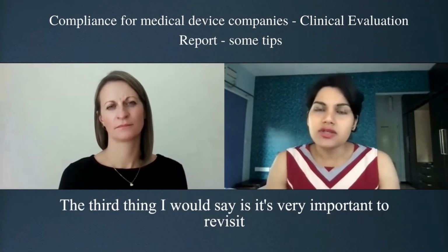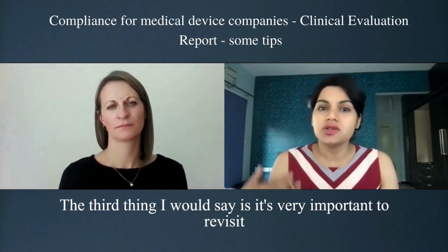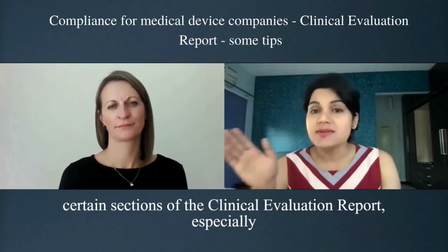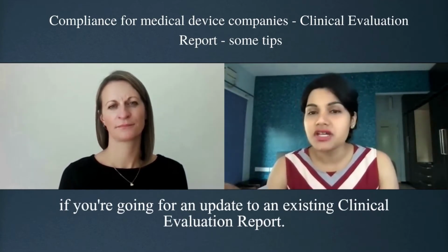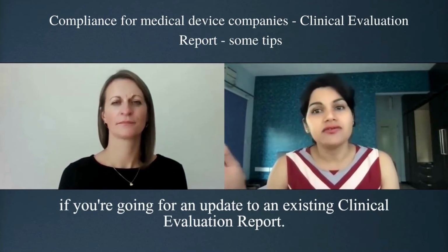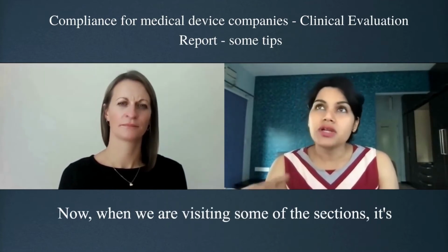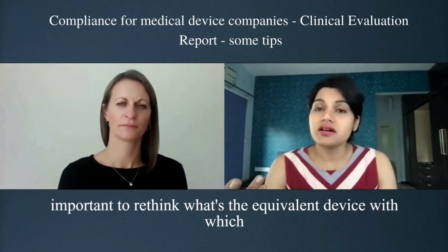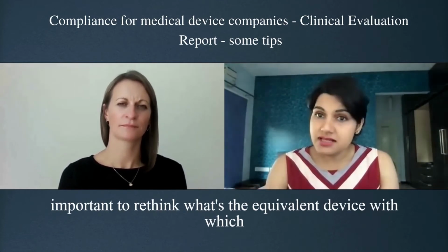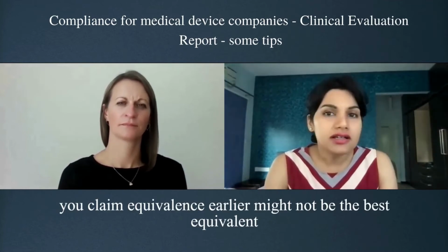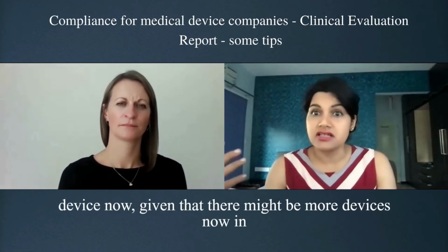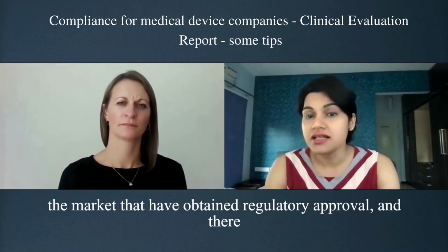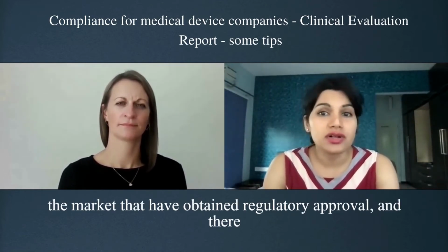That's the second thing to think about. The third thing I would say is it's very important to revisit certain sections of the clinical evaluation report, especially if you're going for an update to an existing clinical evaluation report. When we are visiting some of the sections, it's important to rethink the equivalent device. The device with which you claimed equivalence earlier might not be the best equivalent device now, given that there might be more devices in the market that have obtained regulatory approval.